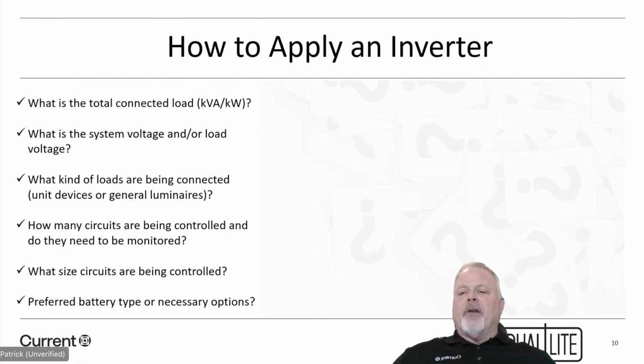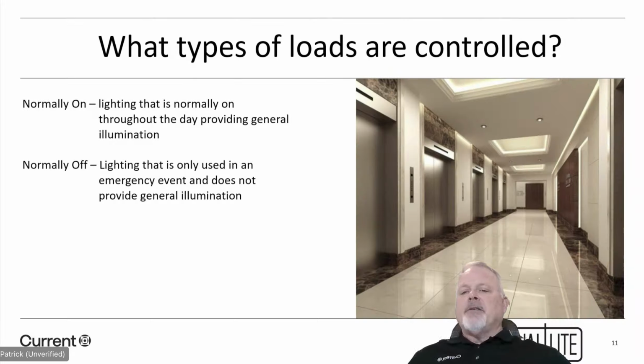Voltage in and out, we need to know that, have to know that, because that determines a couple of things. It determines not only the size of the unit, will a transformer have to be used in the unit itself, and whether or not this is going to be a single phase unit or a 3-phase unit. What kind of loads are being connected, the devices. If you're not aware of this, with lighting inverters, especially on the LSN and our three-phase units, we can add small motors in conjunction with the lighting responsibilities for that inverter. We can do that. We just need to know who the manufacturer is of that motor and the size of the motor, and we can go from there. So this is what comes up, just so everyone knows, most of you probably already do: what types of loads are controlled.